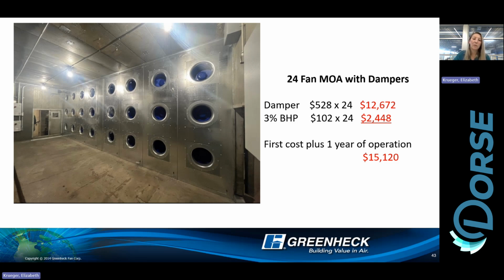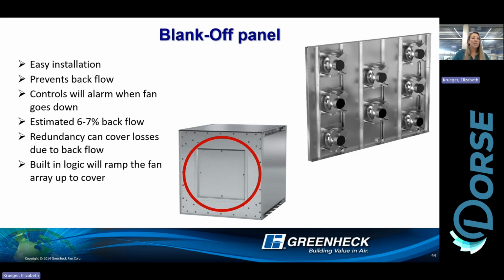You might have more fans in the application, or multiple arrays, multiple air handling units that use way more fans than that. The reason I say no damper is because we've actually tested this. In all that testing, we tested dropping a fan out of an array. What we found is that there's only a 6 to 7% backflow through an opening. So if we lost this fan up here, we'd really only lose 6 to 7%, and the rest of the system would ramp up to cover that.